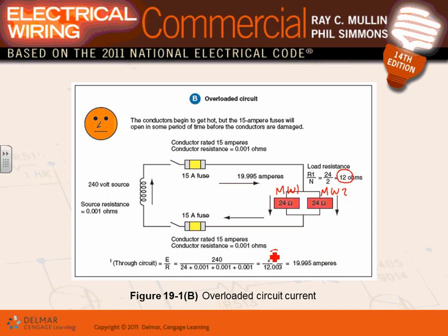Take the 240 divided by 12. Look what happened to the current. Now my current is 20 amp. Now you're pulling how much? 20 amp out of how much? 15 amp. 20 amps out of 15 amp. You know what's going to happen to your circuit breaker or fuse? It's going to open. It's going to take a certain amount of time, maybe a couple of minutes. Bam, your fuse will open. This is called the overload condition.